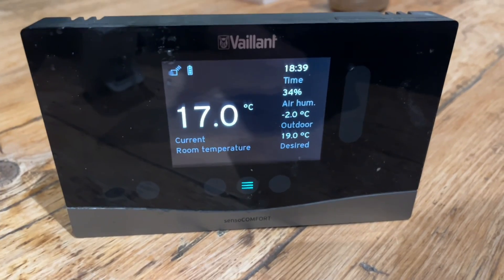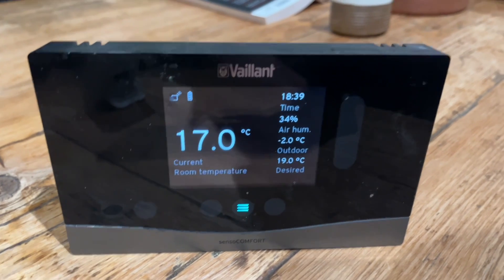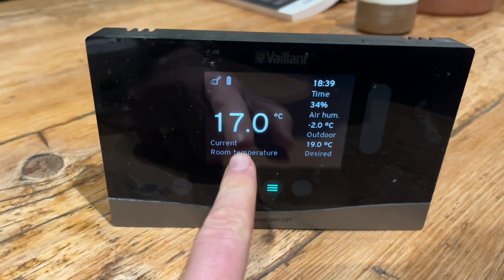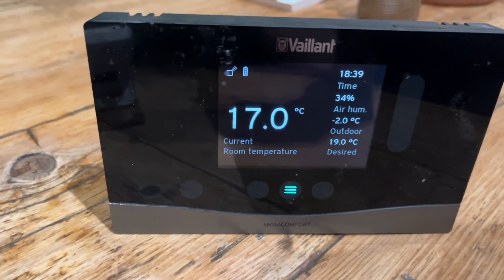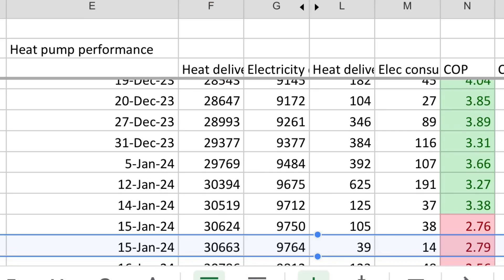So I've been a bit thick — got back in from work, went out to take the recycling out, and then all the way back in I'd not closed the back door properly. So the temperature dropped loads. Maybe the data from today, Monday, is going to look pretty bad. Anyway, we'll get it back up to 19. Because I'd been a bit thick, I decided to reset the metering and took a reading just before bed on Monday night. Over Monday afternoon and evening, with a slightly cracked open back door, we used a further 14 kilowatt hours of electricity to deliver 39 kilowatt hours of heat to get us back up to 19 degrees. This was a COP of 2.79 and another £2.66 cost for that 10 hours in the afternoon.